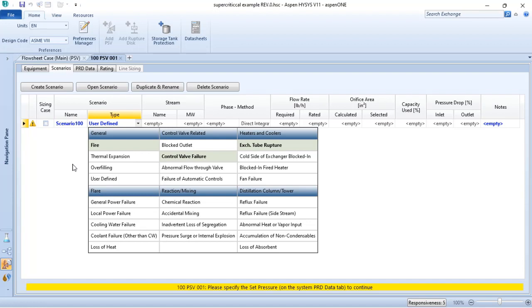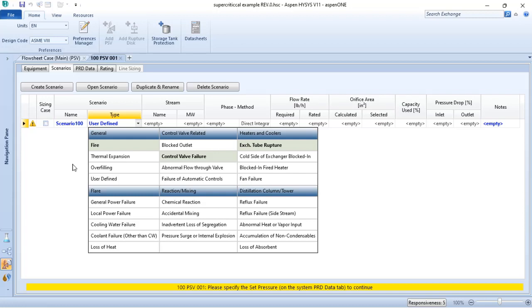Another scenario of overpressurization is a control valve failure. Most often, when we are dealing with pressure control, you want to decrease a high pressure to a low pressure and you need to consider the scenario of having this control valve full open.